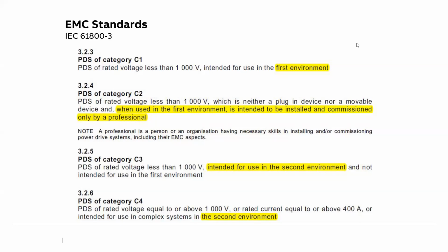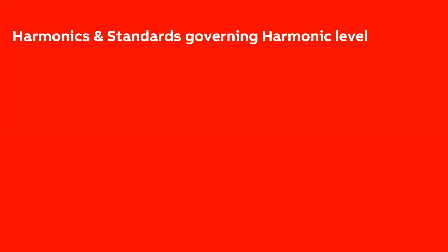So if we are talking about VFD, then VFD, as per this standard, falls under the C2 category. Then C3 and C4 categories of filters are also suitable if it is in the second environment. So that was about the EMC. So EMC, we have seen, is high frequency noise or radio frequency noise, and it needs some filter to filter it out. So the filters available are C1, C2, C3, and C4. And as per the code, the recommended category of EMC filter for a product like VFD is the C2 category. So this was about EMC. Then we'll go to harmonics. Now, what is harmonics?